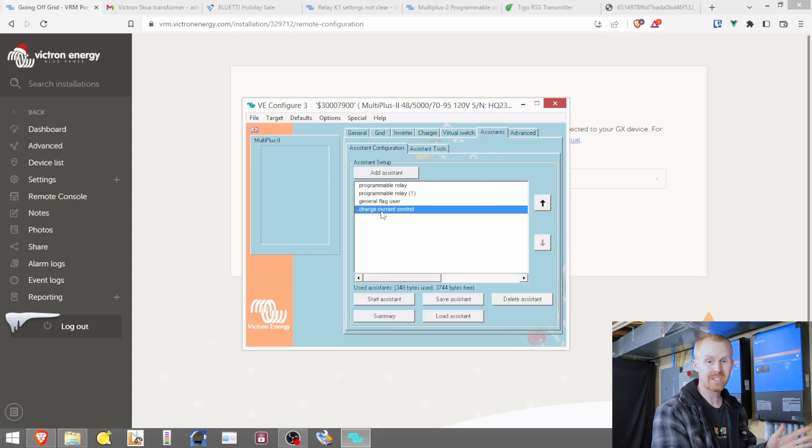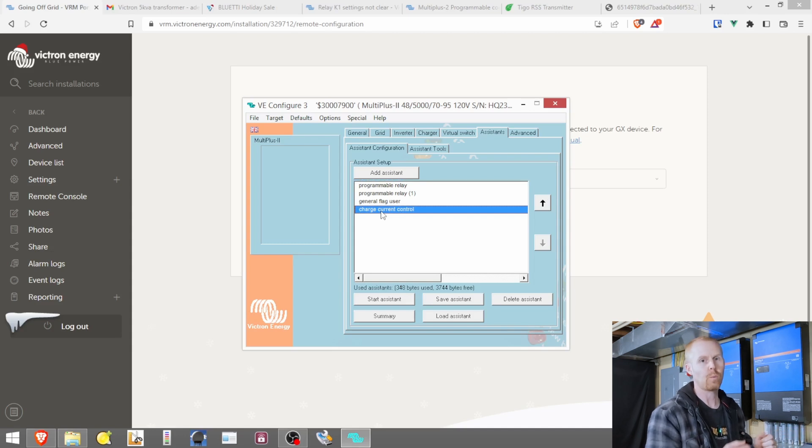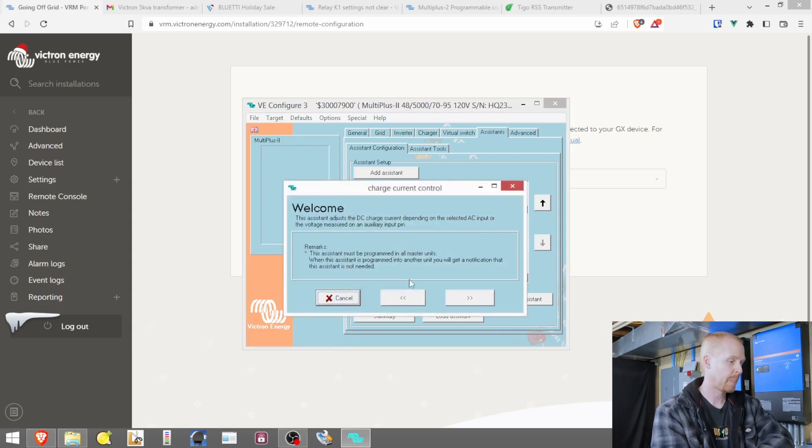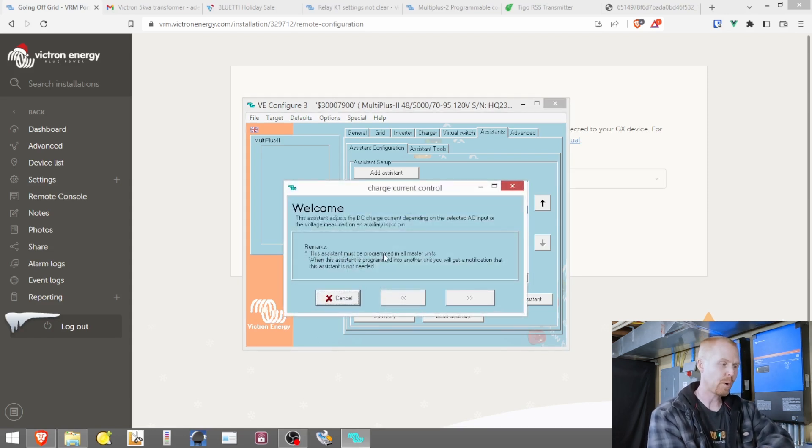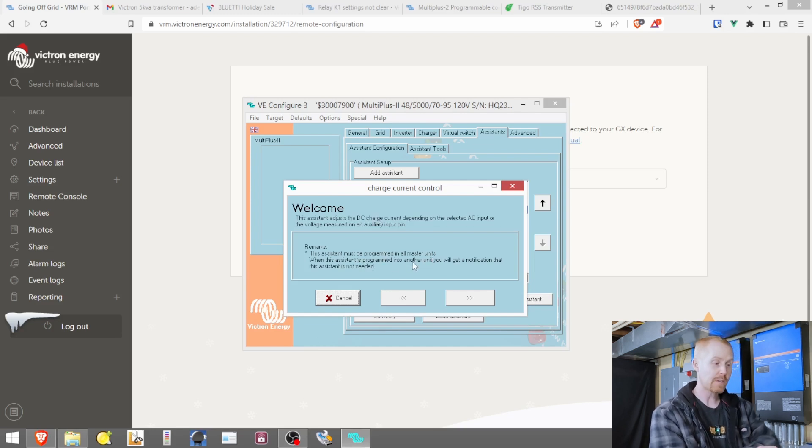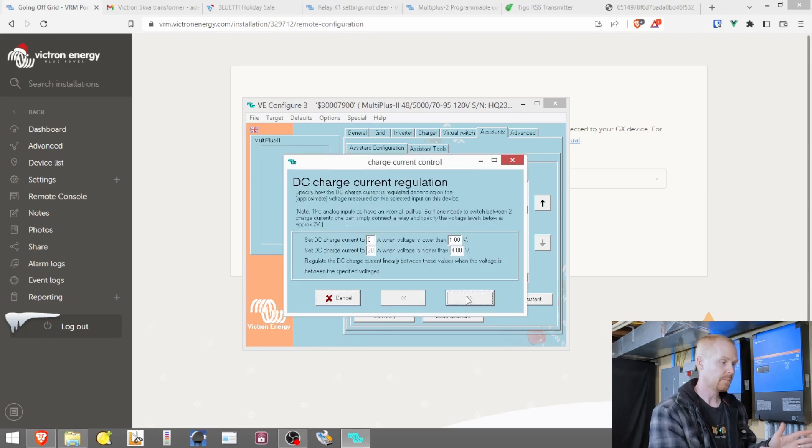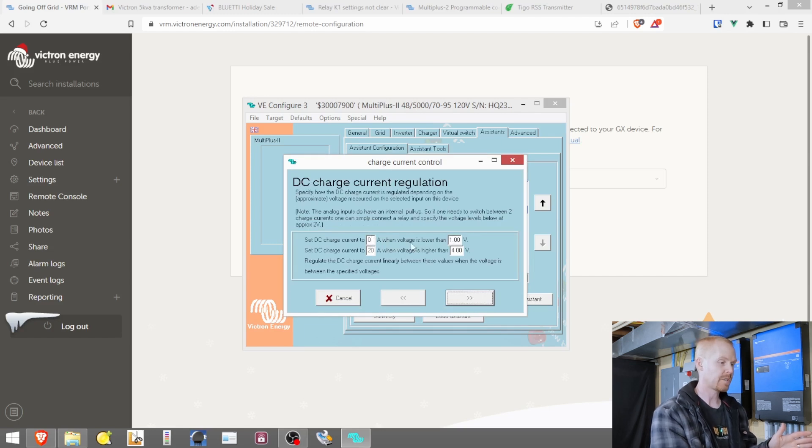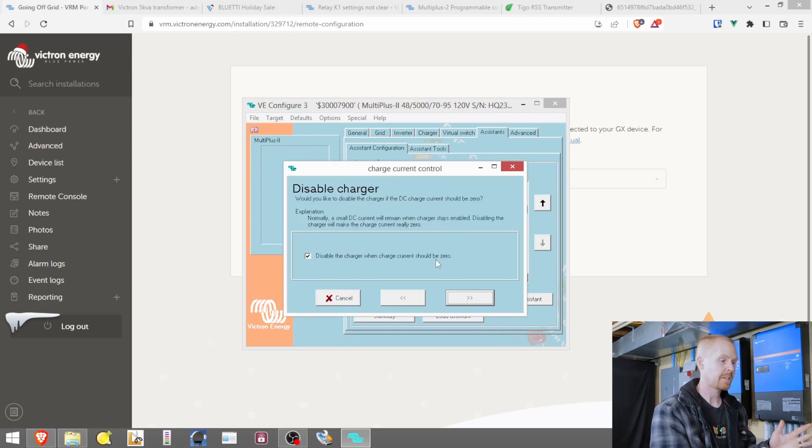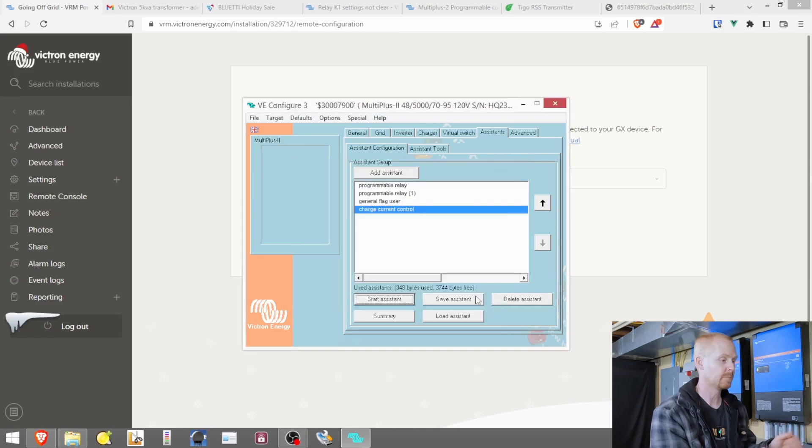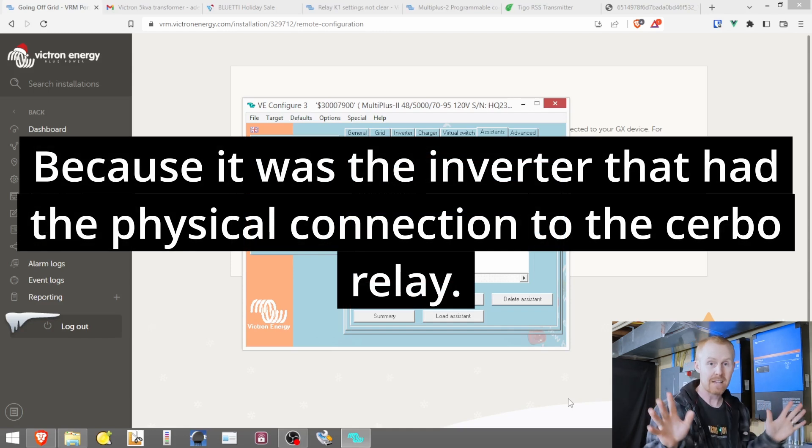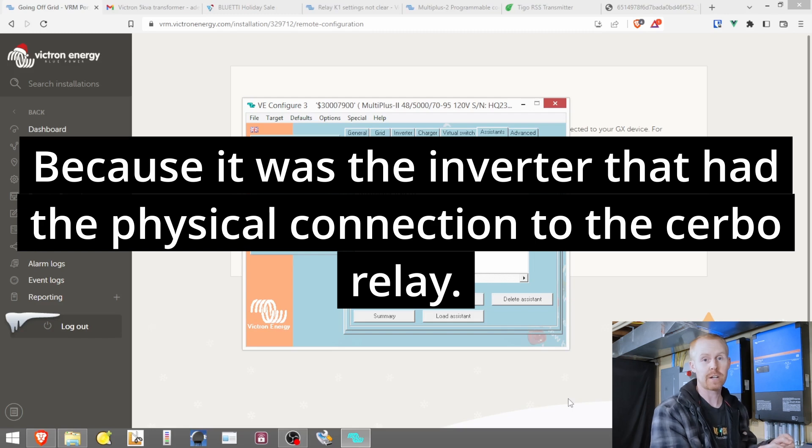And this charge current control assistant is the one that controls whether or not these inverters are going to charge from the grid. So if I start this assistant, we can see right here, this assistant must be programmed in all master units. When it's programmed into another one, you're going to get a notification that it's not needed. So we have this set to use aux 2 and set the charge to zero when the voltage is lower than one and set the charge to 20 amps when the voltage is higher than four volts. And then disable when the charge current should be zero. And that's it. It's very basic, but I only added it to this inverter thinking that it was the master over the entire system.